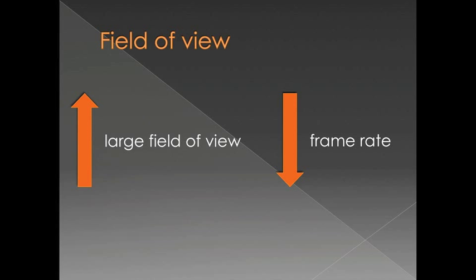The field of view also has an impact on the frame rate, so if you have a large field of view, it's going to take longer for those echoes to reach the deep portions of the tissue. It's also going to take longer if you have a wider sweep. So increased field of view decreases the frame rate.